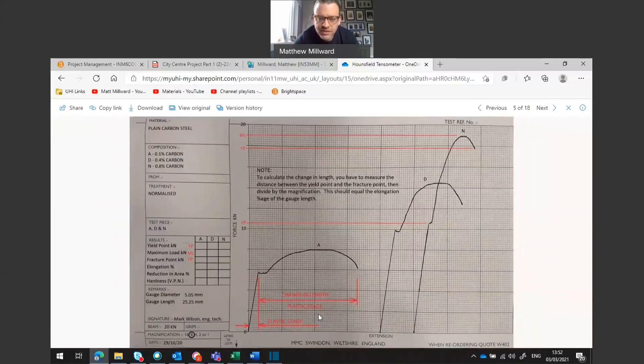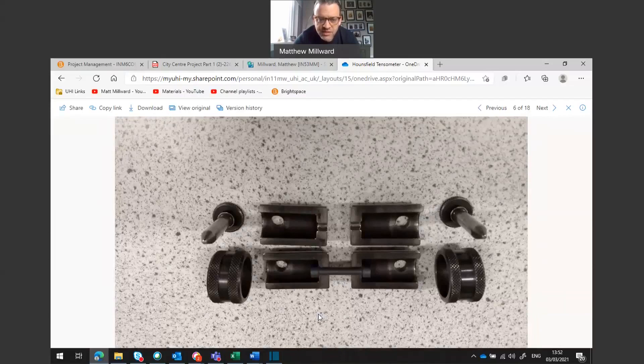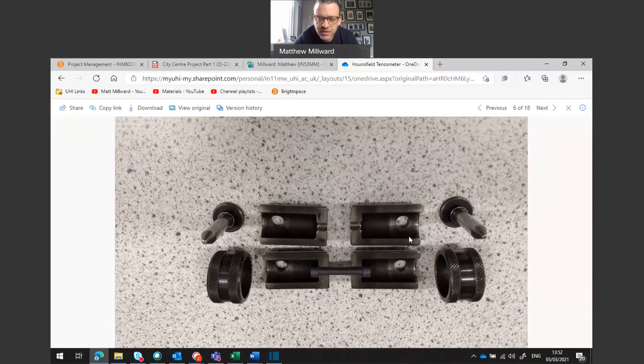As you can see with this graph, which I will come back to in just a moment — this is how the sample is put into the Hounsfield tensometer. We have clamps at either end where it is put into the machine and tensile load can be applied. You can see here that we have some pins and rings that will clamp these together and apply the load nice and evenly.